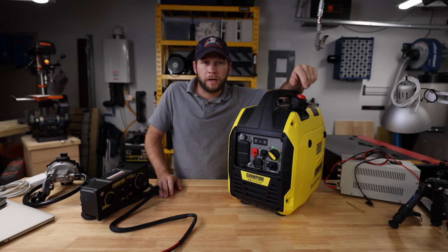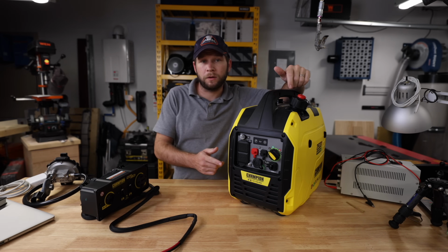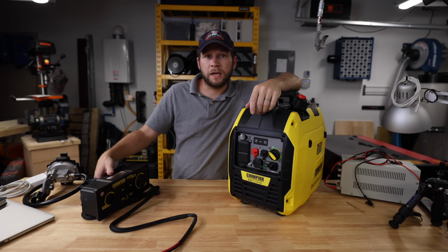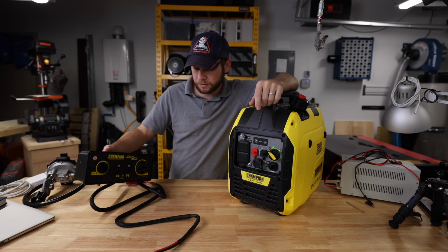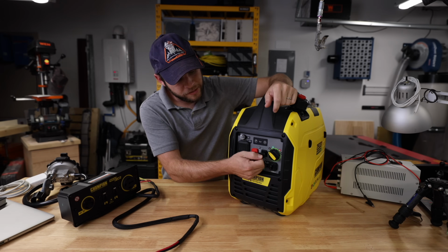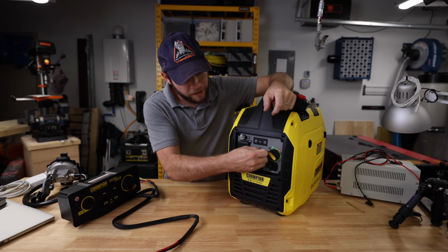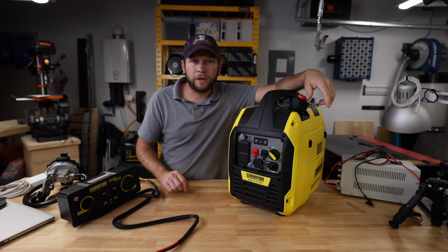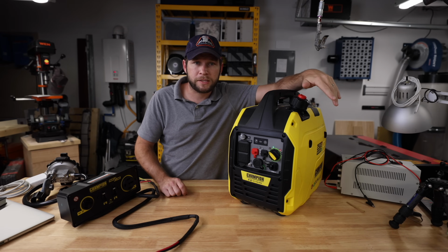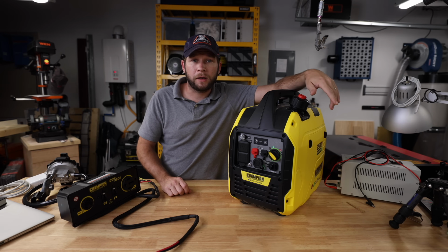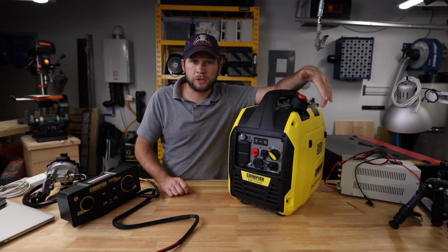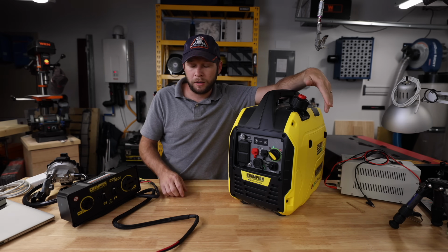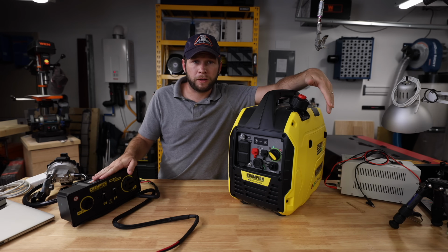Now, the smaller inverter generators usually have a parallel capability, and as you can see behind me over here, I've got a second one, and those connect with something like this parallel box. And this parallel box connects into these parallel inputs, or outputs in this case, and basically ties the inverters together. You start up one inverter and let it warm up and get settled. Then you start up the other one, and the other one syncs its inverter to the one that's already started. So they produce the power simultaneously, essentially doubling your output through the output of this parallel box.